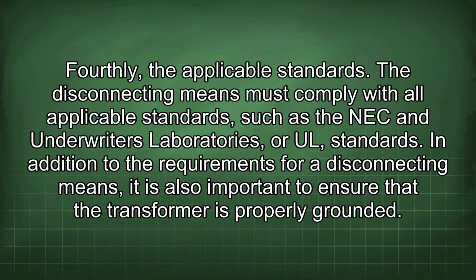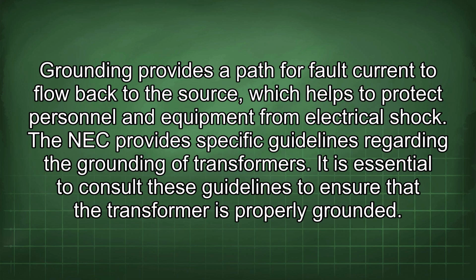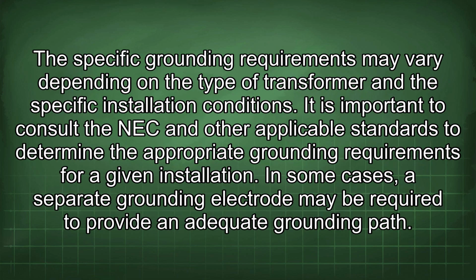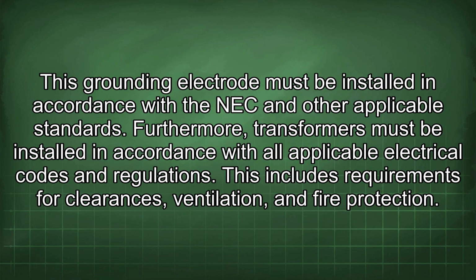transformer is properly grounded. Grounding provides a path for fault current to flow back to the source, which helps to protect personnel and equipment from electrical shock. The NEC provides specific guidelines regarding the grounding of transformers. It is essential to consult these guidelines to ensure that the transformer is properly grounded. The specific grounding requirements may vary depending on the type of transformer and the specific installation conditions. It is important to consult the NEC and other applicable standards to determine the appropriate grounding requirements for a given installation. In some cases, a separate grounding electrode may be required to provide an adequate grounding path. This grounding electrode must be installed in accordance with the NEC and other applicable standards.